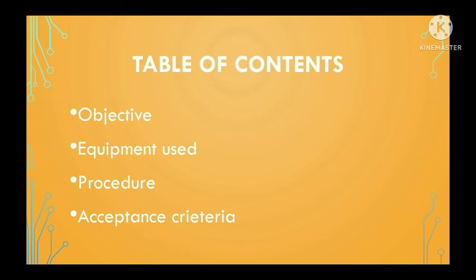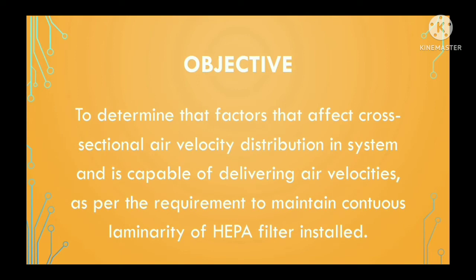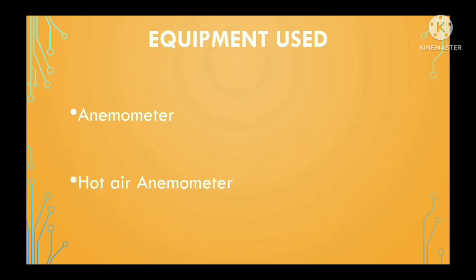If you are new to this channel, please subscribe. First, we will see the objective for air velocity check. Air velocity check for HEPA filters is done to determine factors that affect cross-sectional air velocity distribution in the system and to verify it is capable of delivering air velocities as per requirement.